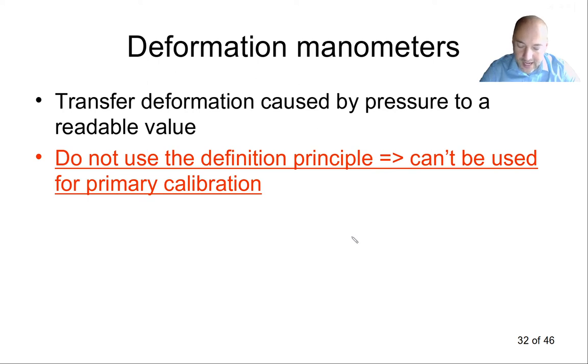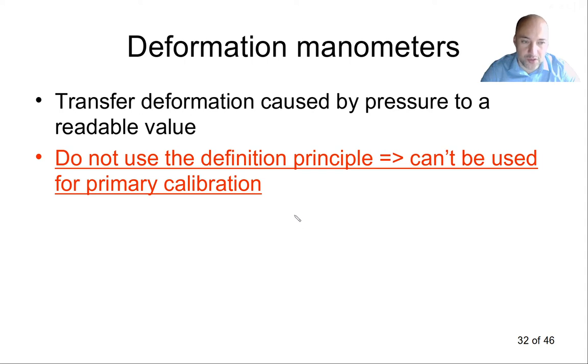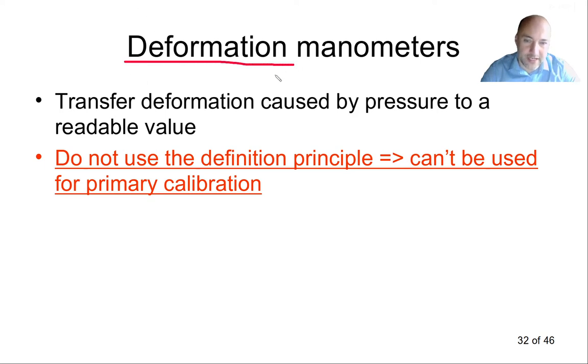In industrial systems you need to have pressure gauges that are quite robust, so they are fine with vibrations, fine with temperature changes, with dirt, and so on. For this reason we need to use a different principle. Industrial pressure gauges use deformation — we change the shape of some element, for example a diaphragm, and this change of shape is proportional to the pressure we measure. So all the pressure gauges we will see today will be based on deformation of something.